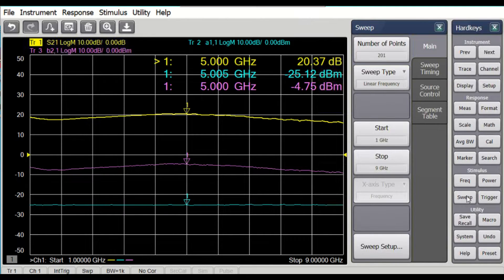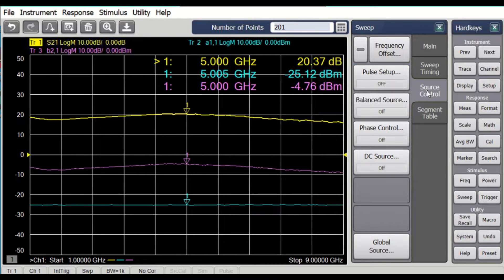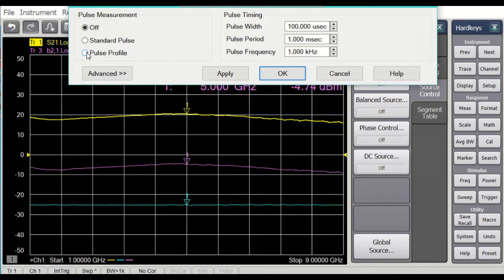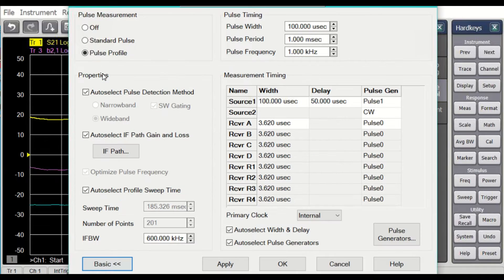When we want to do pulse, we have this source control pulse setup. In the pulse setup, we can do different kinds of pulse. Standard pulse means doing a pulse S-parameter measurement — a swept frequency S-parameter measurement — but just doing it in a pulse condition. I'm first going to show you pulse profile, because pulse profile will show us how the pulse shape will look. So I'll select pulse profile.